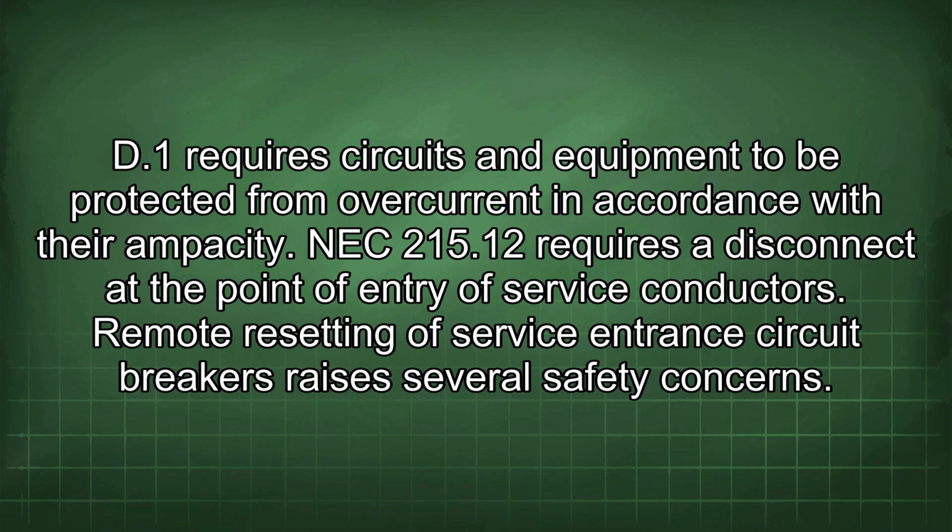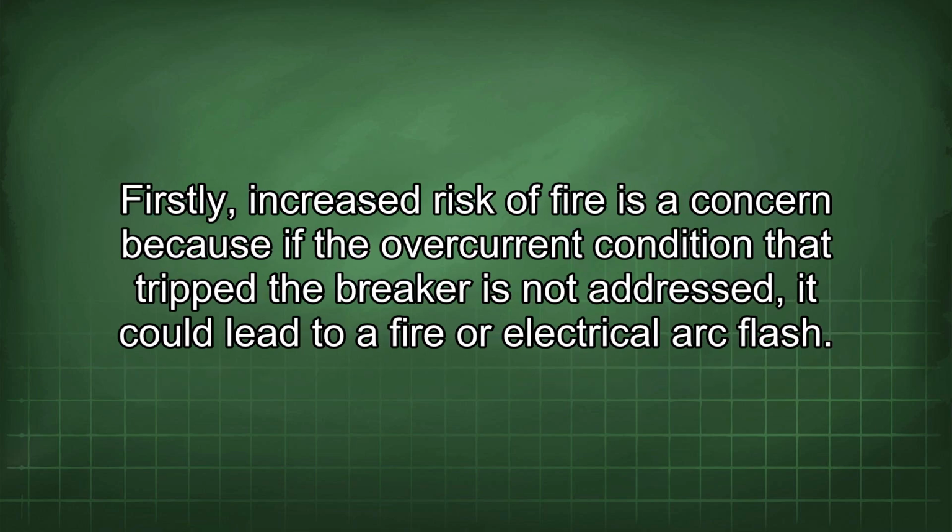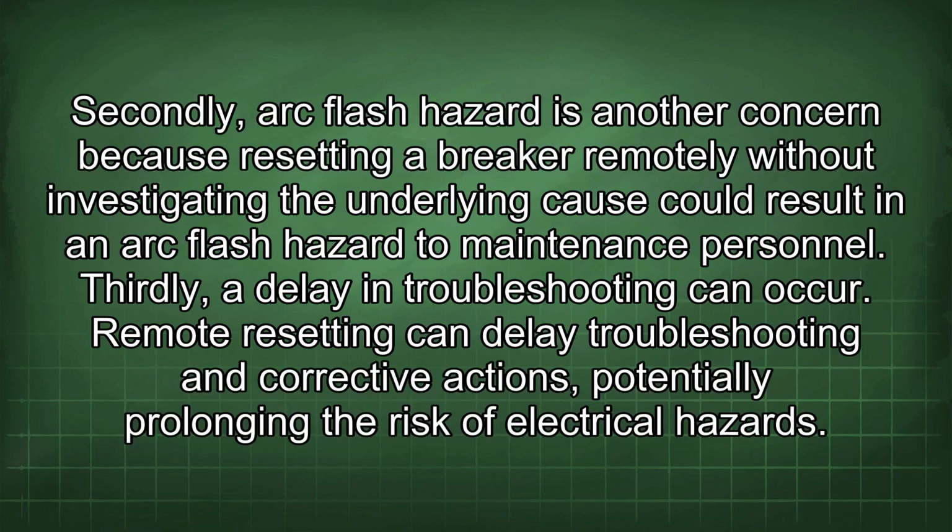Remote resetting of service entrance circuit breakers raises several safety concerns. Firstly, increased risk of fire is a concern because if the overcurrent condition that tripped the breaker is not addressed, it could lead to a fire or electrical arc flash. Secondly, arc flash hazard is another concern because resetting a breaker remotely without investigating the underlying cause could result in an arc flash hazard to maintenance personnel. Thirdly, a delay in troubleshooting can occur. Remote resetting can delay troubleshooting and corrective actions, potentially prolonging the risk of electrical hazards.